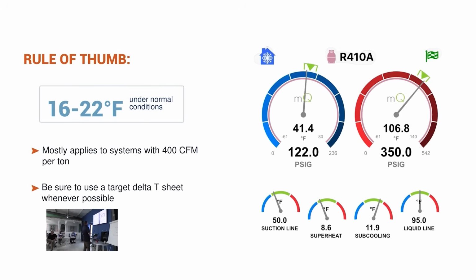Again, rule of thumb: 16 to 22 degrees. But you have to know that's based on a 400 CFM per ton calculation in a more normal climate. In your climate, you're typically going to be a little bit lower, and you can compensate for that by running a little lower evaporator airflow. As you get that evaporator airflow lower, it compensates for the fact that you have more moisture. The thing I want you to know is when you have a low delta T, that could be due to a problem, but often it's just due to the fact that you have high humidity. Make sense?